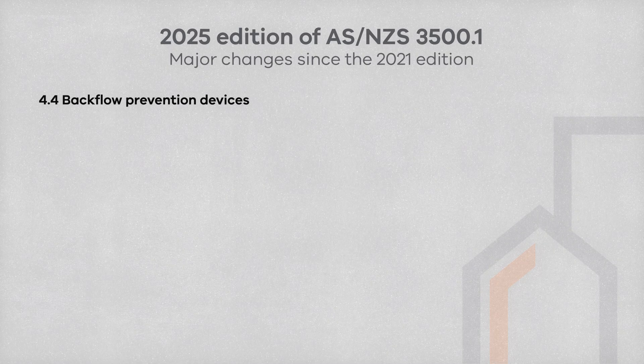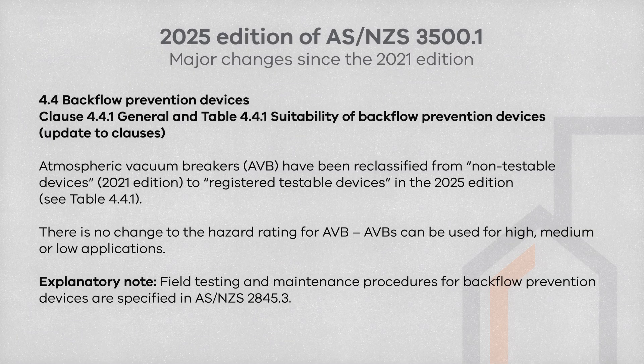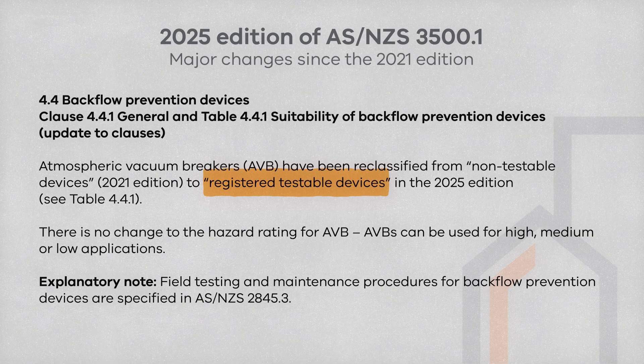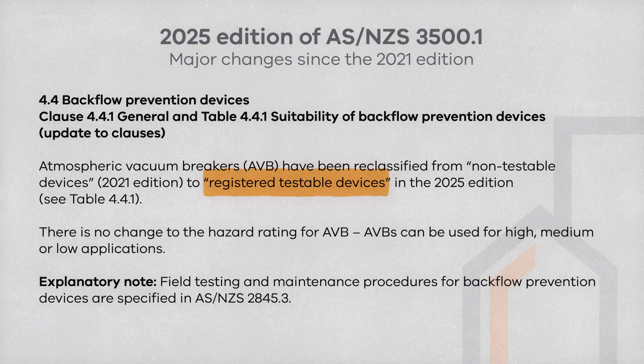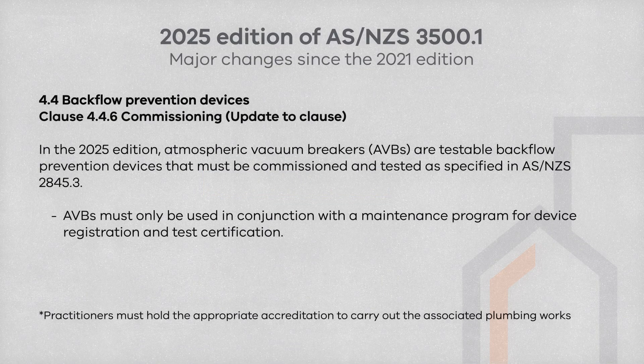There are a few updates to be aware of regarding backflow prevention devices in Clause 4.4. Atmospheric vacuum breakers, commonly called AVBs, have been reclassified from non-testable devices to registered testable devices in the 2025 edition — as found in Table 4.4.1. The hazard rating remains the same, being suitable for high, medium or low hazard risks. As this reclassification lists AVBs as testable devices, they must be commissioned and tested as required by AS/NZS 2845.3, the standard that applies for field testing of testable devices.